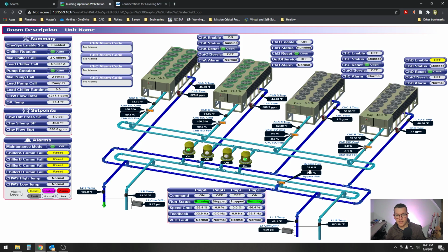So this is 590, we're at 37.6, 35.5, and then we undershot, so then it's going back up. It's going to start climbing. Boom, right there. It's probably going to keep climbing. 45, 46. It's trying to maintain 550 right here. So again, in the simplest terms, the only thing this bypass valve controls is the minimum flow over the chiller.